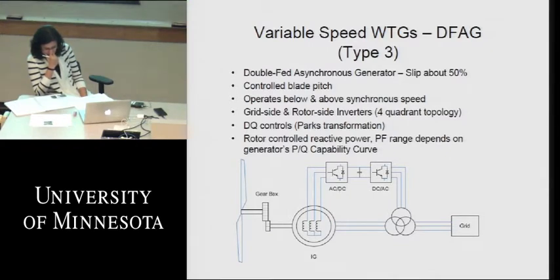So the rotor's reactive power capability is defined when you design the generator itself. It's got limitations to it as such, but the power factor range really depends on this machine's active power and reactive power capability curve. Those of you that have taken electrical machinery and have seen synchronous generators, this is known as the D curve on those types of machines. But the curve looks entirely different for these types of wind turbines. Next slide.